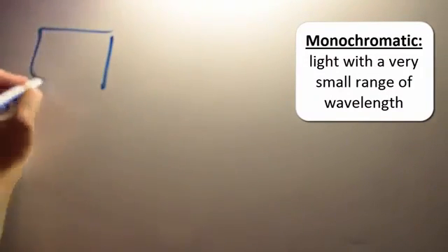So how do we measure that? We measure that with a monochromator, which is something that measures one wavelength at a time. And a good example of that is a single beam spectrometer. So that works by having first a light source, and then the wavelengths that come off that light source are sent to a monochromator, which only observes one wavelength because it's only interested in one wavelength. And then that wavelength comes out and hits a sample of your liking, and then that wavelength passes through the sample and hits a detector. That detector tells you about that wavelength.